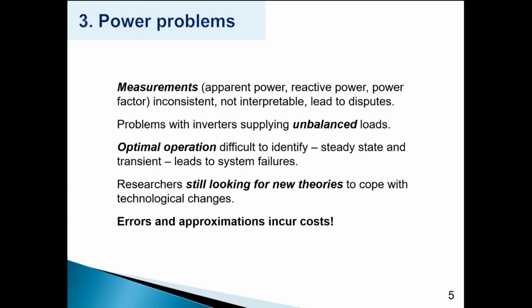And these things are bringing problems. There are problems in making measurements of apparent power and reactive power and power factor that are being reported from all sorts of different directions and landing some utilities in the courts. They give inconsistent quantities or values for the quantities measured. If you take out one meter and put in another, you don't necessarily get the same reading. And the reading that you're getting is not interpretable in terms of physics. I'll come back to that later. And this is what leads to the disputes.